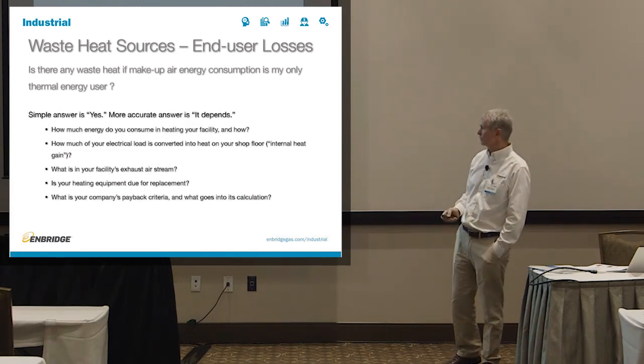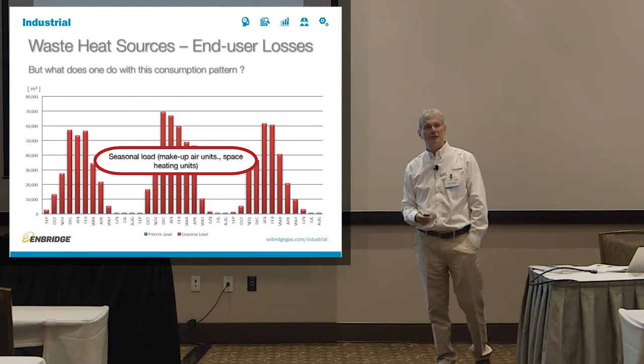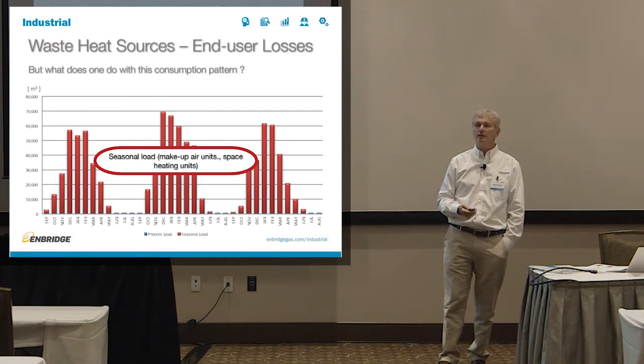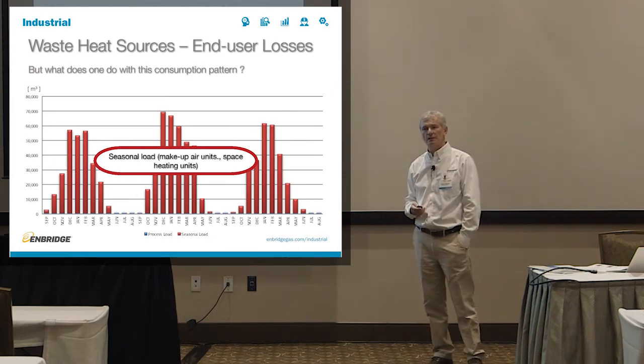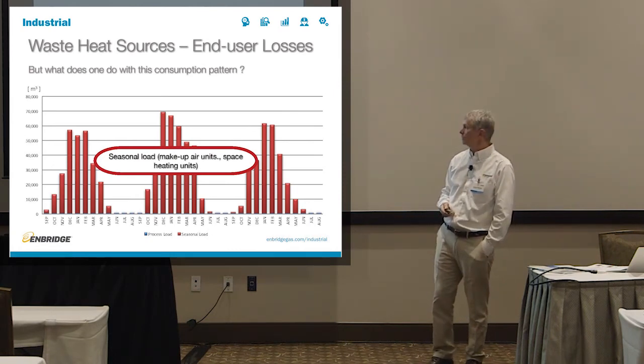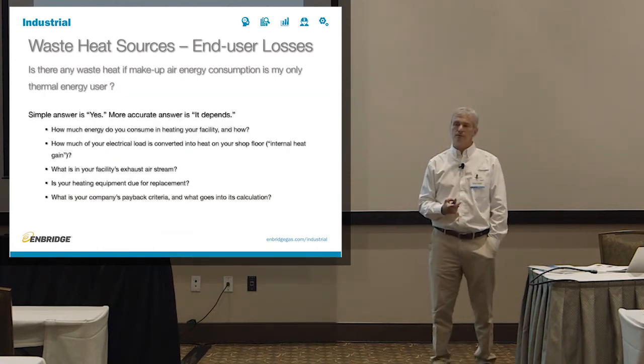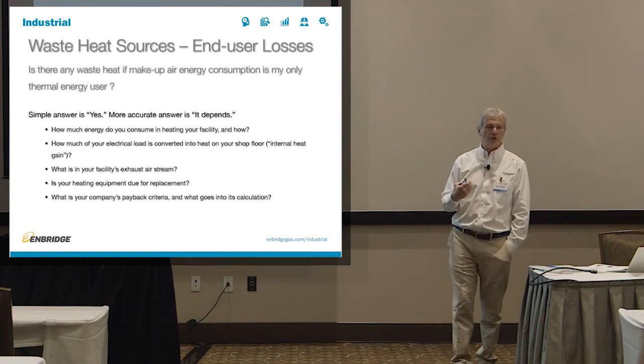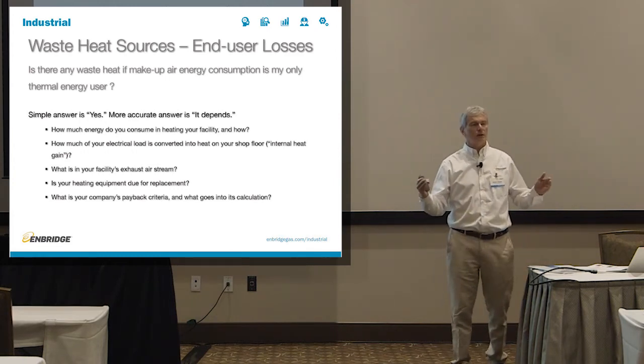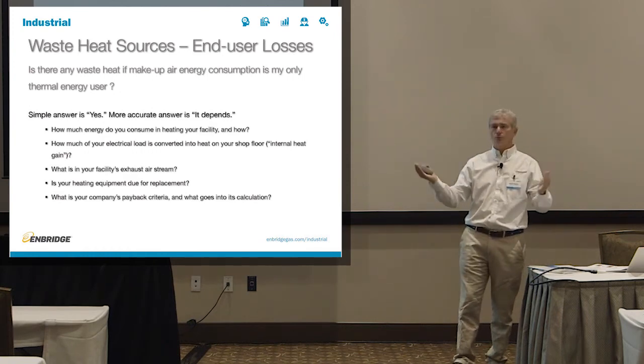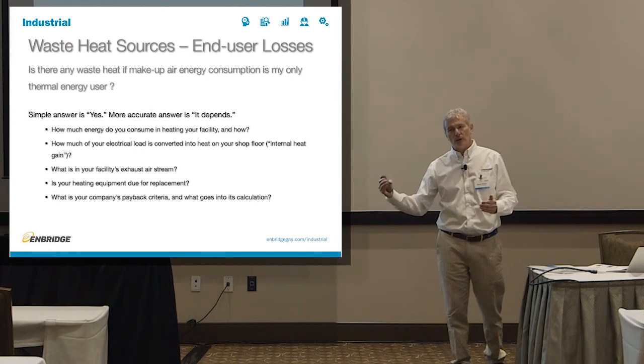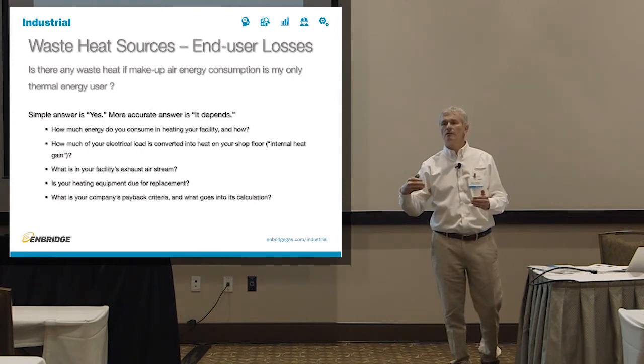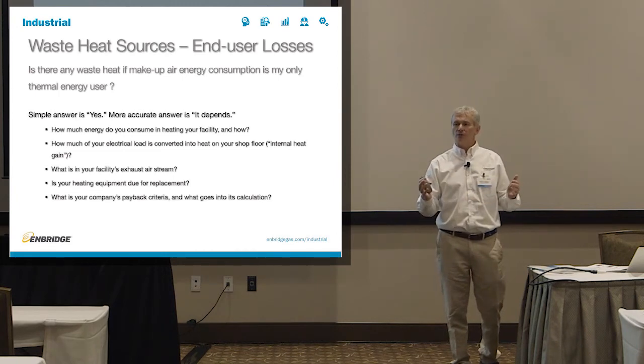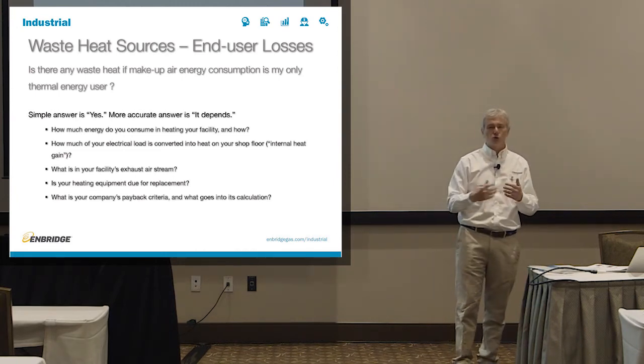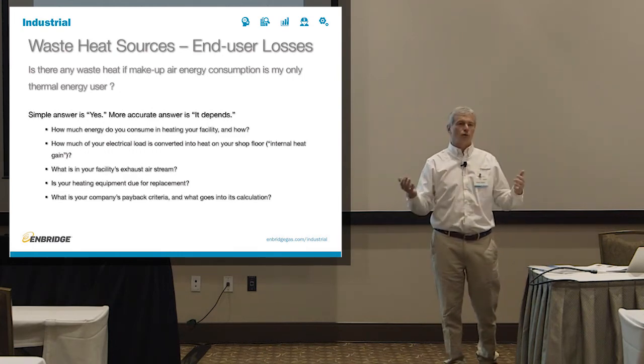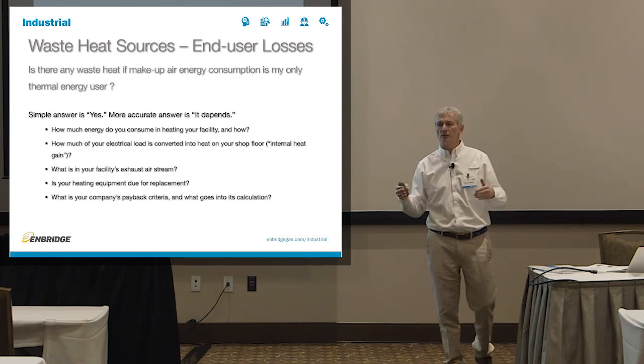Because if your consumption profile looks this way, you have no process heat, therefore you don't have any natural gas waste heat to speak of. But you still might have waste heat from your electrical consumers of energy. So do you know what your internal heat gain is? And a rule of thumb that I always use, if you think about a facility as a closed loop system, if this room is our facility, and if you put 100 kilowatts into this facility, and you don't ship anything hot off the press, you get it at ambient temperature, you ship out your product at ambient temperature. So of those 100 kilowatts, probably 95 kilowatts will be turned into internal heat gain.